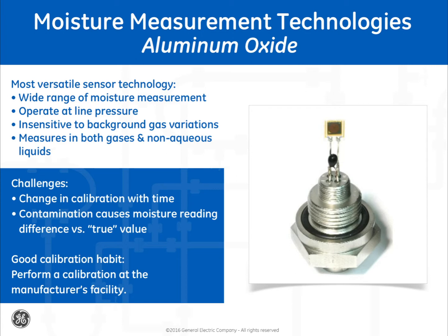Aluminum oxide moisture sensors, along with other metal oxide sensing technologies, are the most versatile moisture analyzer technologies. They offer a very wide range of moisture measurement, allowing the operator to see the analyzer dry down from ambient moisture, typically in the 10 degrees C dew point range, or over 1% water vapor, to the measurement point of interest, sometimes below minus 100 degrees C frost point, or single-digit part per billion moisture contents.